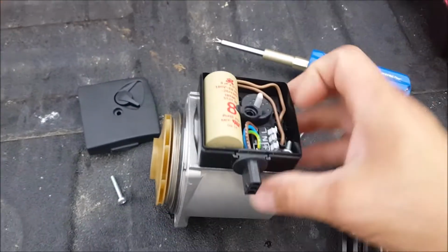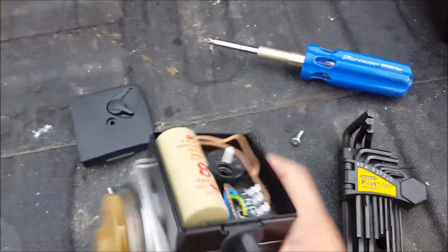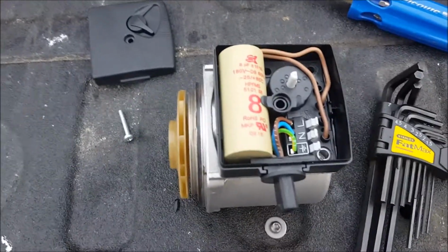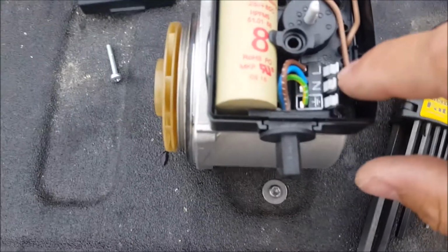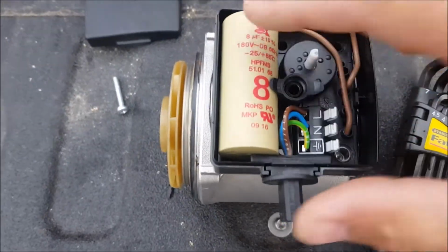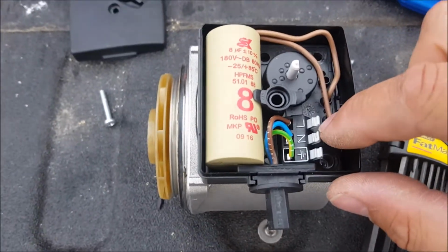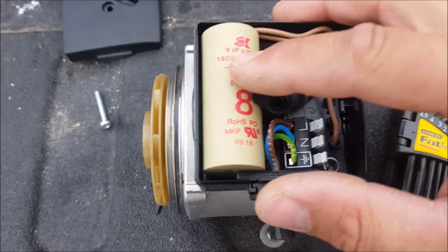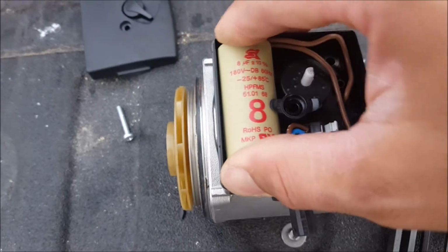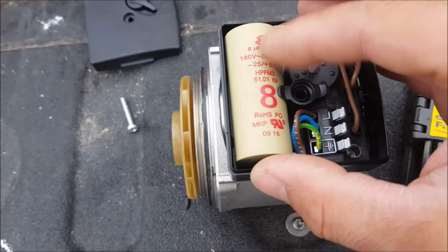Okay, now in here you'll see these two connectors are plugged in. This is your capacitor. You have a voltmeter that does capacitance - you can unplug this, put the meter on there, and make sure it's 8 microfarads. You gotta have 8 microfarads. So get a voltmeter that can measure capacitance and check that out. If that's bad, it won't work.